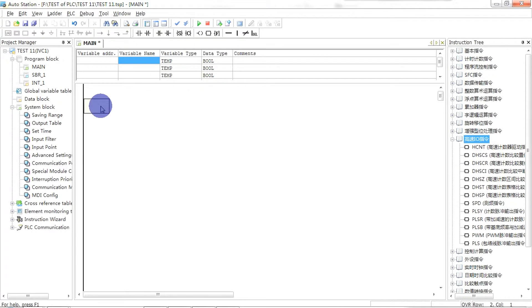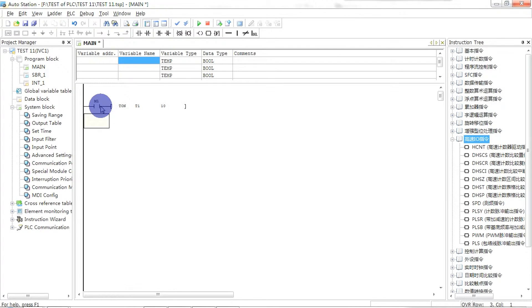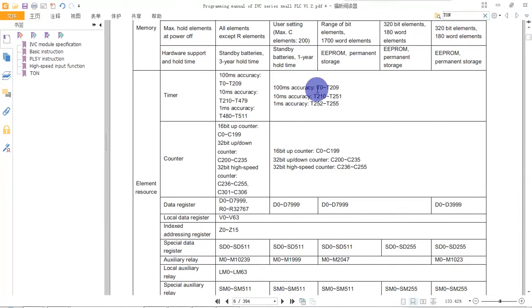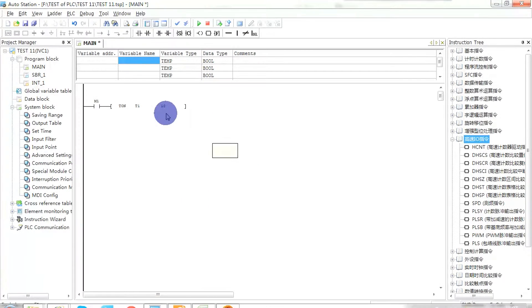For example, we need to make a contact to start the timer. We use the TON instruction and one of the timer elements, T1, and set the time. From the table, we can see T1 is in this range, where the unit is 100 milliseconds. This means 10 equals one second.